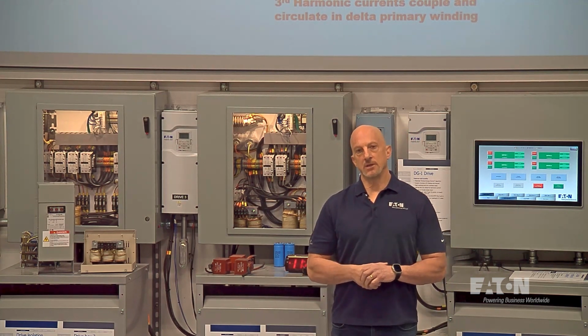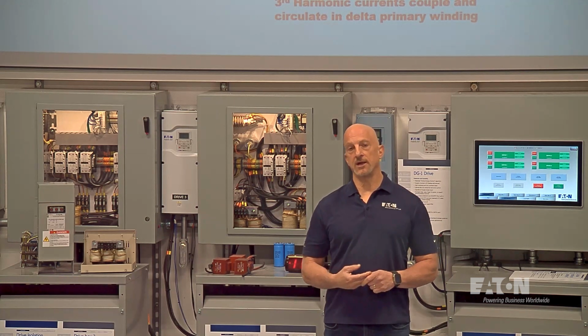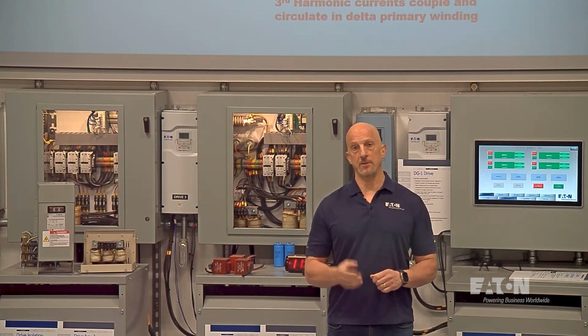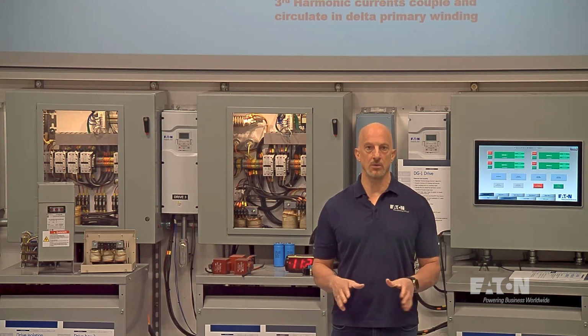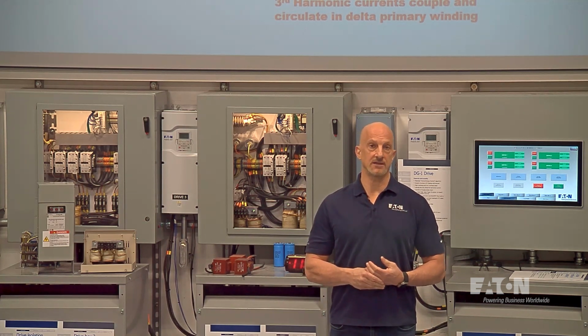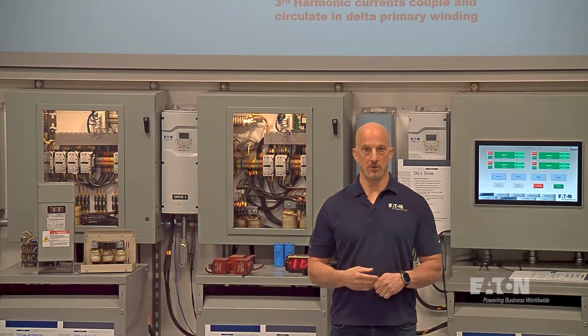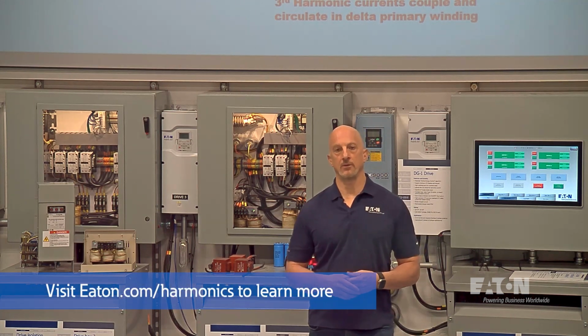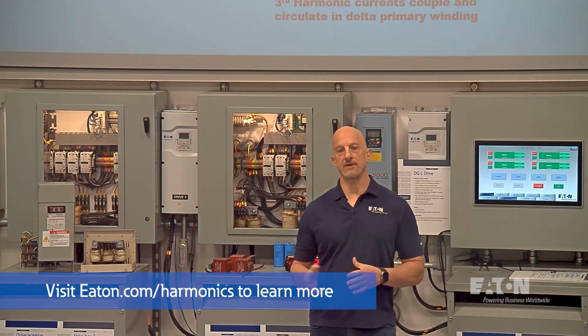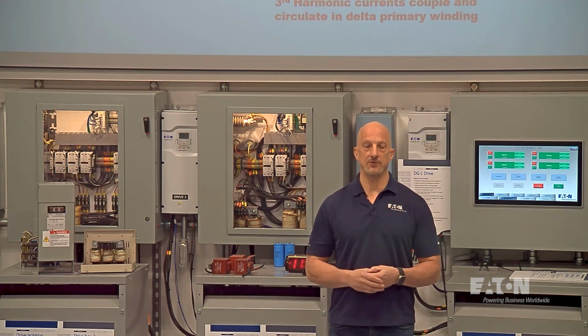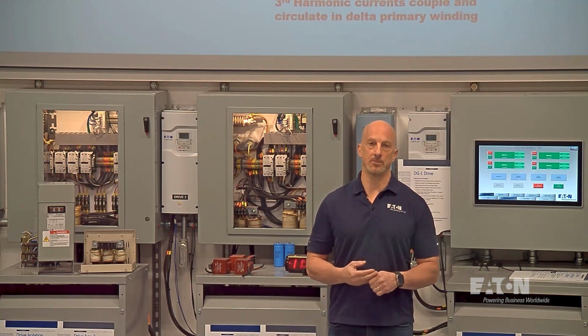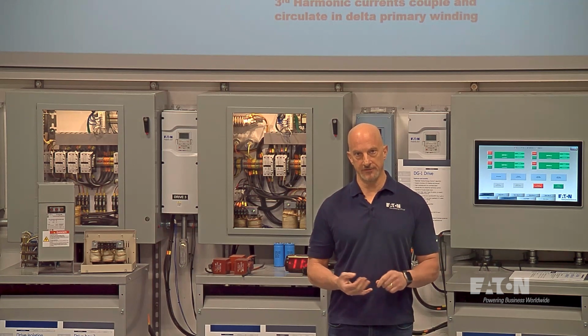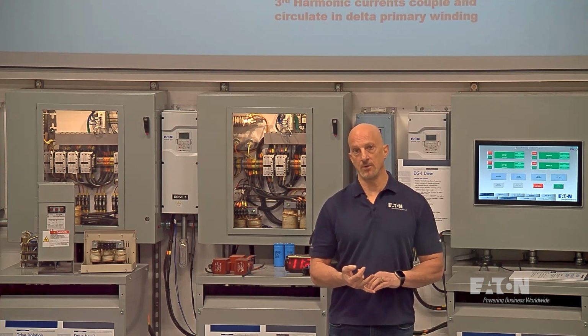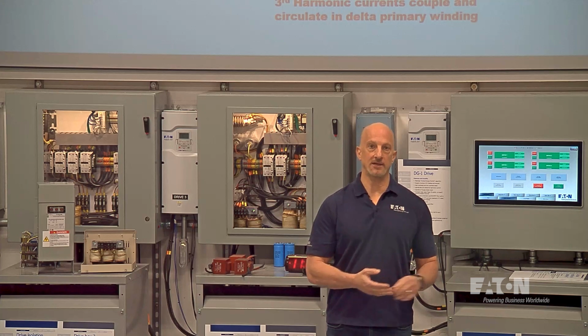The other thing that's going on today with a lot of computer power supplies is they're power factor corrected. Those power supplies have very low total harmonic distortion. In fact, it's kind of a bit of a misnomer. They're actually harmonically corrected power supplies, and the waveforms are very linear. So where we used to have to worry about third harmonics on computer power supplies like in servers, it's not as big of a deal today, but definitely know the loads that you're applying as to whether or not you have to double the size of the neutral on the panel board or switchboard, and all the way back to the transformer itself.